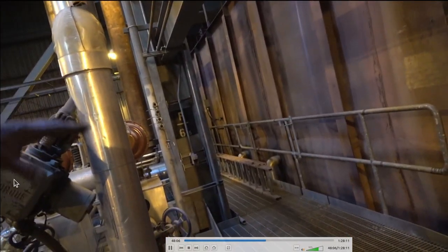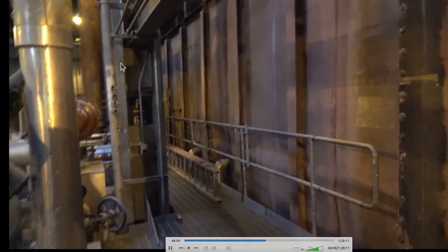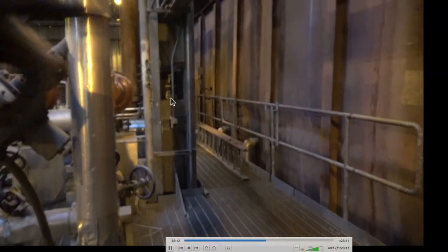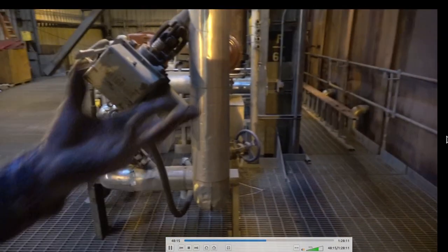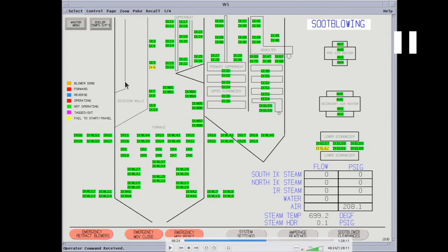Back to the boiler penthouse — this is the soot blowing over here. The steam for the soot blowers is pressure-controlled and flow-controlled for each blower, depending on how hard you need to blow that section of boiler. Inside here is all the piping for the top of the boiler. This is the soot blowing screen — you have division walls, bullnose, finishing superheat. Basically, steam comes out of the drum through the top roof tubes, through primary superheat, fed back to division walls. It's sprayed down to about 860 degrees for the division walls, then those sprays on top spray it down for the finishing superheat to about 1,005 on the outlet.